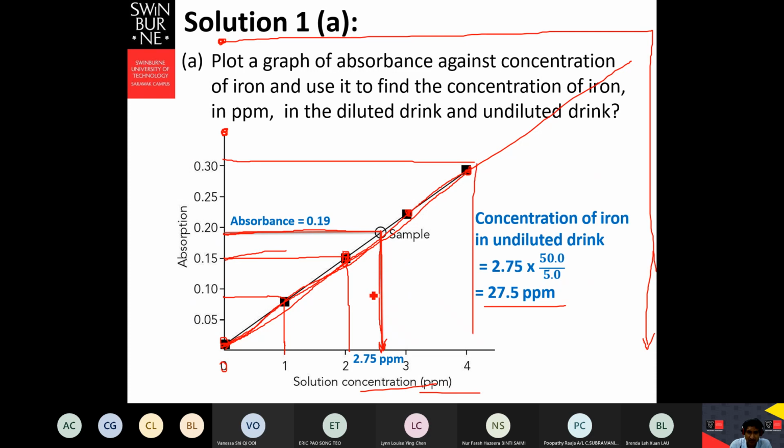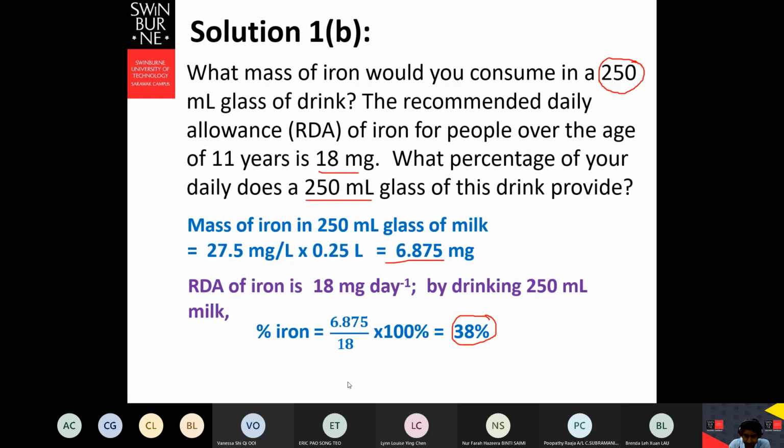Only until this range is the curve calibrated. If you take a reading beyond it, probably it will be correct, probably not, we do not know, but it is not accepted because it is beyond the calibration range.